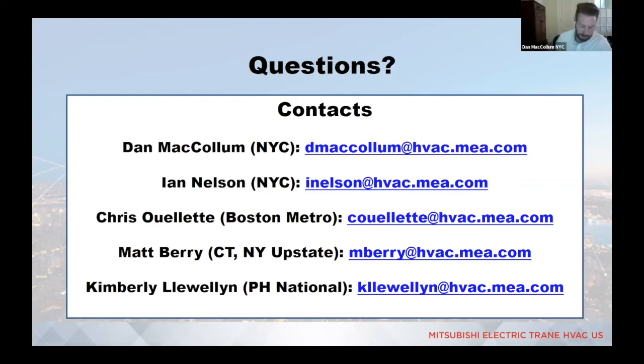So let me first address the condensate question. It's a simple yes. The approach is going to be pretty much the same that you're familiar with in terms of condensate removal from a mini split. The indoor units will have a built-in lift mechanism if they're at or above the ceiling level. So any ducted style units or cassette units will have a built-in lift. And then if that's not enough, or if you're utilizing a wall mount style unit, you'd want to consider an auxiliary condensate pump if you can't do a gravity drain system. And in terms of your second question, can you reiterate?